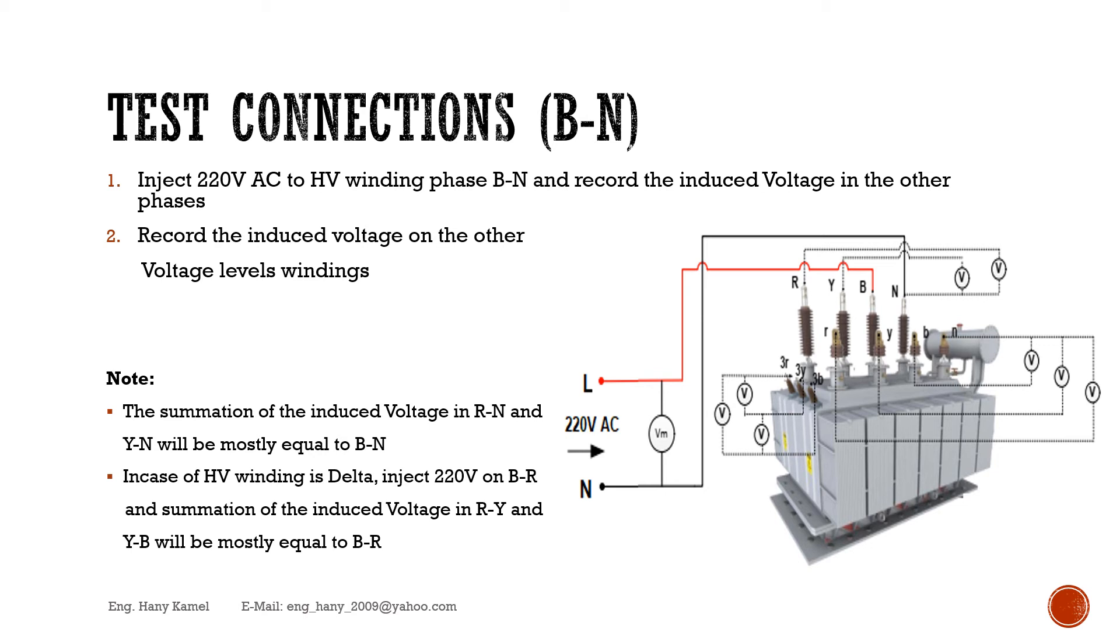In case of HV winding is delta, inject 220 volts on B-R and summation of the induced voltage in R-Y and Y-B will be mostly equal to B-R.